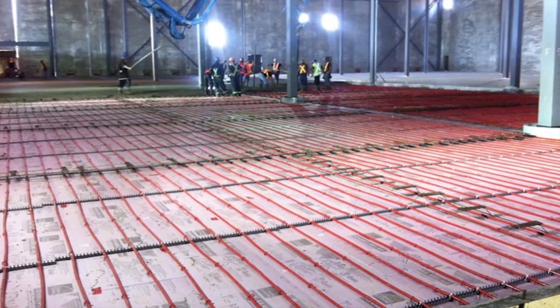My responsibility was to meet ASHRAE 189.1 indoor environmental quality, which includes ASHRAE 62.1 on ventilation and ASHRAE 55 with thermal comfort. Having a large source of hot water in the center of the occupied space inspired a very efficient HVAC system. The tank we chose allows you to store water at 180 degrees Fahrenheit, and heat is transferred from the tank to make 100-degree water that we will pump through little polyethylene tubes in the concrete foundation.